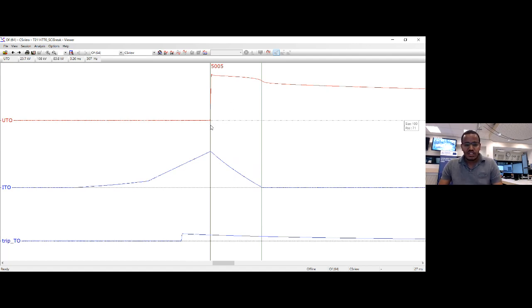What we mentioned as very important is that the circuit breaker produces a voltage. The voltage can be seen from this red trace on the top. So the counter voltage, the TIV, I can show you the value. A value of about 121 kV could be produced by this circuit breaker for about 3.5 milliseconds, as you see here. I would like to show you with a better graph. I think this must be okay. Yes, here.